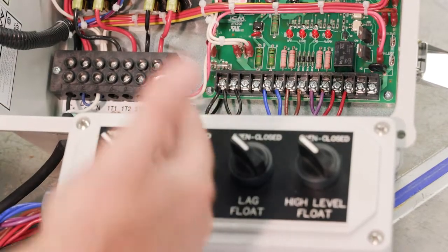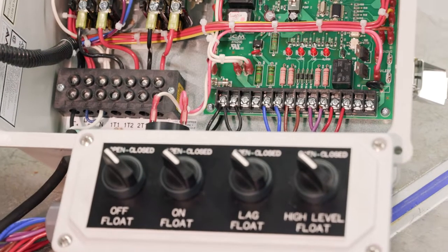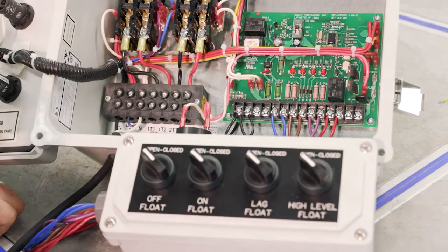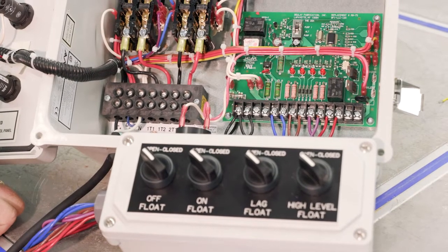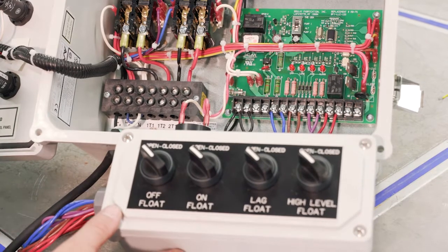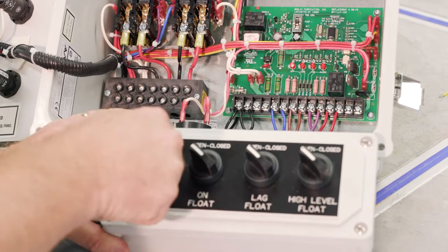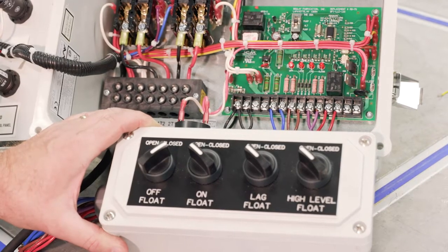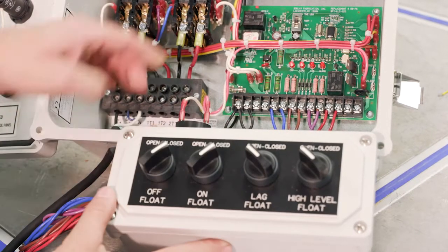Let's do that sequence again, because we have an alternating system, and we should see the other pump automatically turn on, because it alternates. So let's go through that system again. Then off float first, light is on, nothing is happening, on float, light is on, should be this pump here, contactor pulls in.